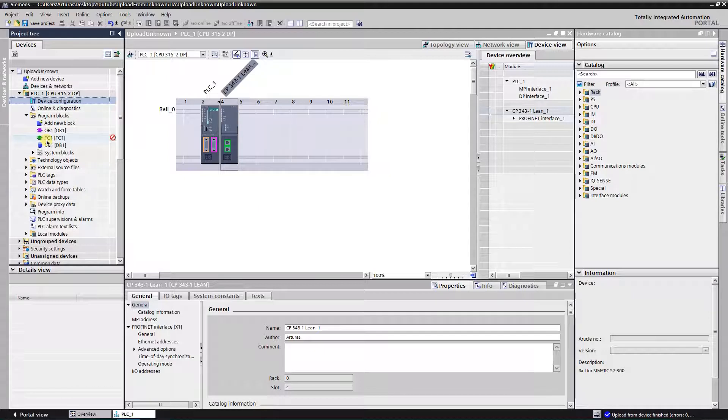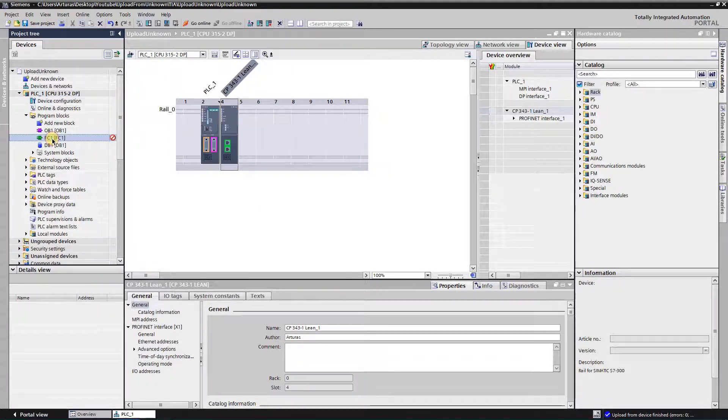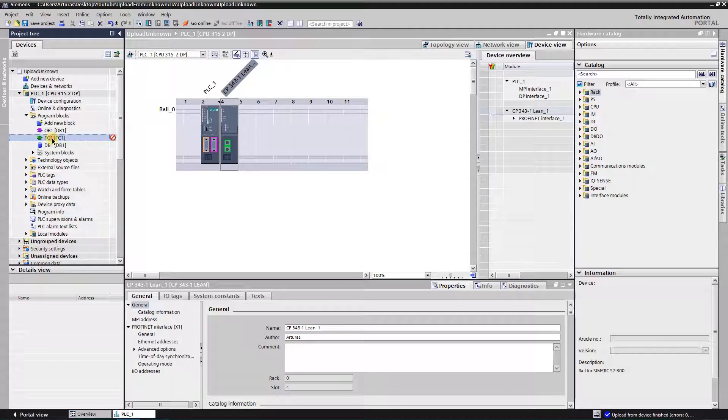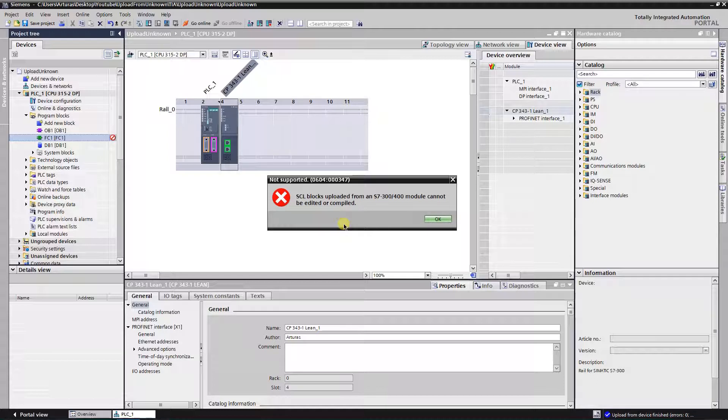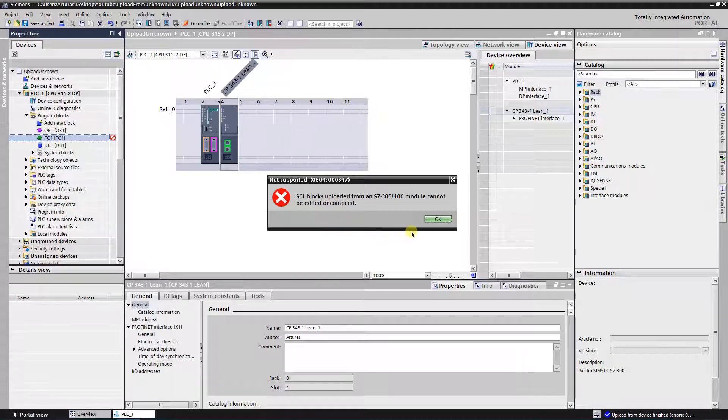Here we have a first problem. Block FC1 was created in SCL language. Unfortunately, blocks that were created in SCL language are messed up on the upload. The only option to fix it is to generate it from source if you have one.